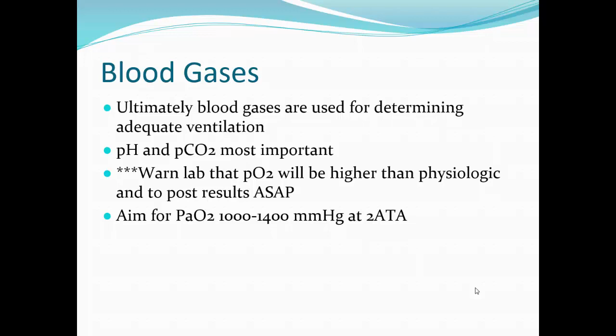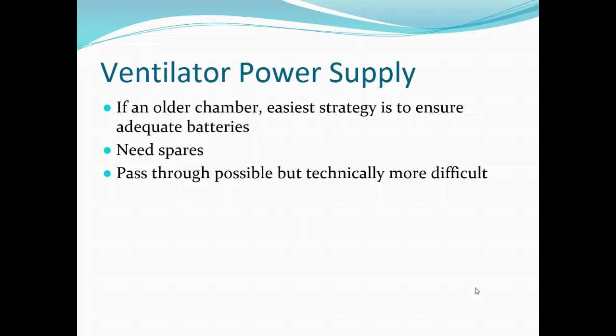Power supply: the easy strategy is batteries, but typically you need to include spare batteries. Usually it'll last for about 2 to 3 hours, but if you're doing your longer extended treatment tables, you'll need to send new batteries into the chamber through the lock or have them with you there. You can do pass-throughs, but again, it's technically difficult when you're trying to bore a hole, or have the technicians set up a hole through the chamber through which to pass your plugs.